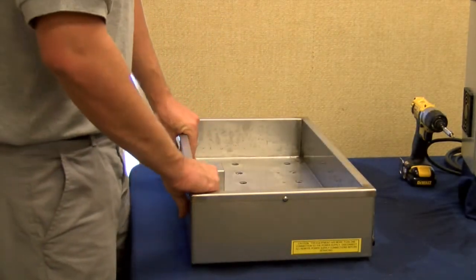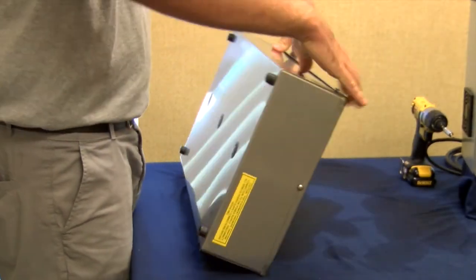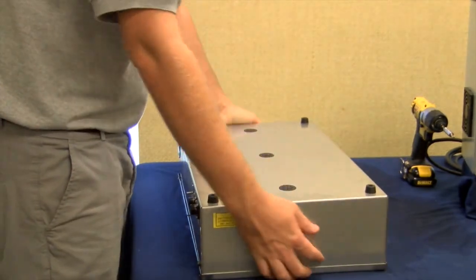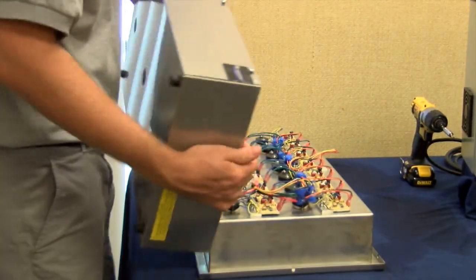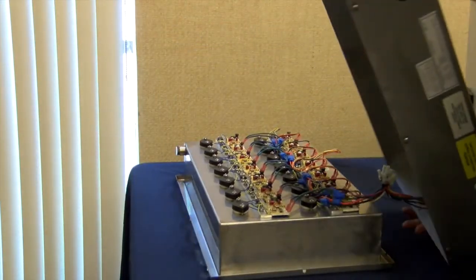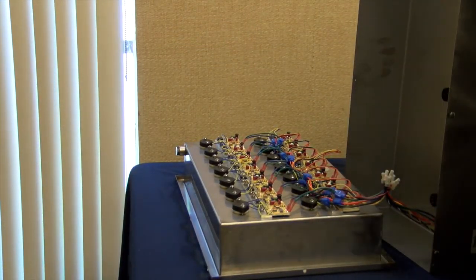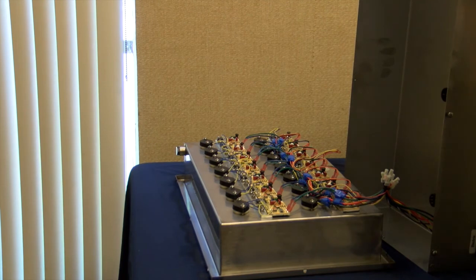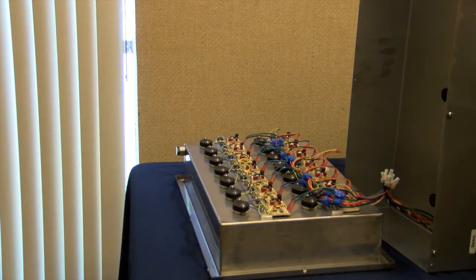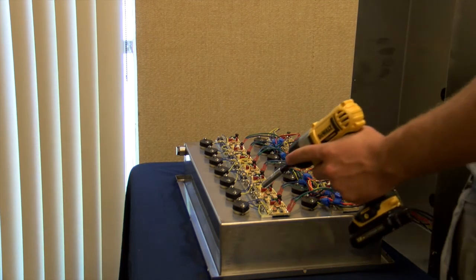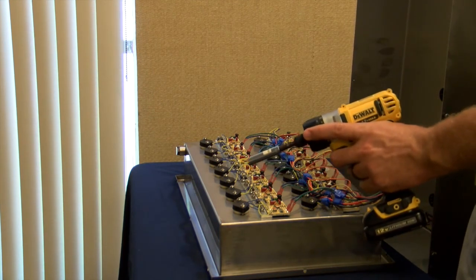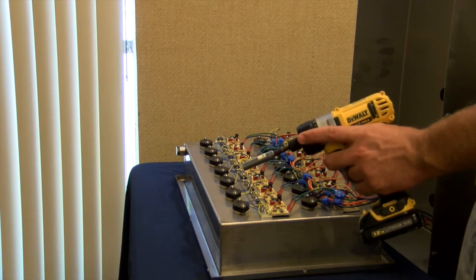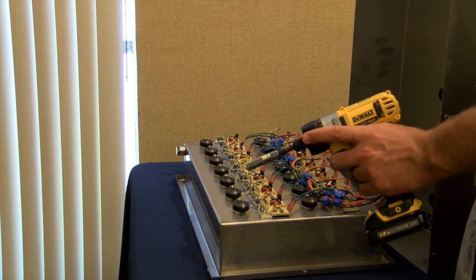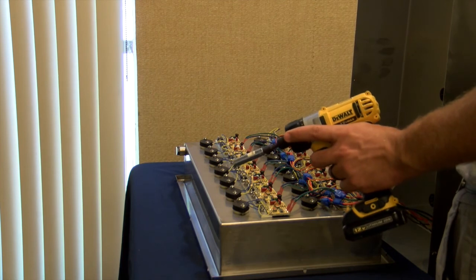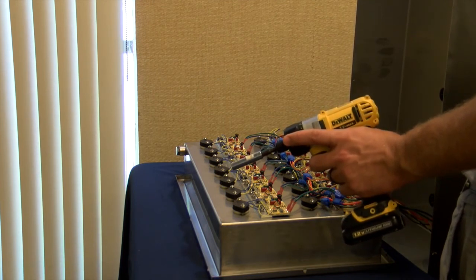Once those screws have been taken out, simply flip over the unit and take off the bottom pan. Notice you will need a 5/16 socket to take off each of the number 6 keps nuts that secure the transducer and print plate.